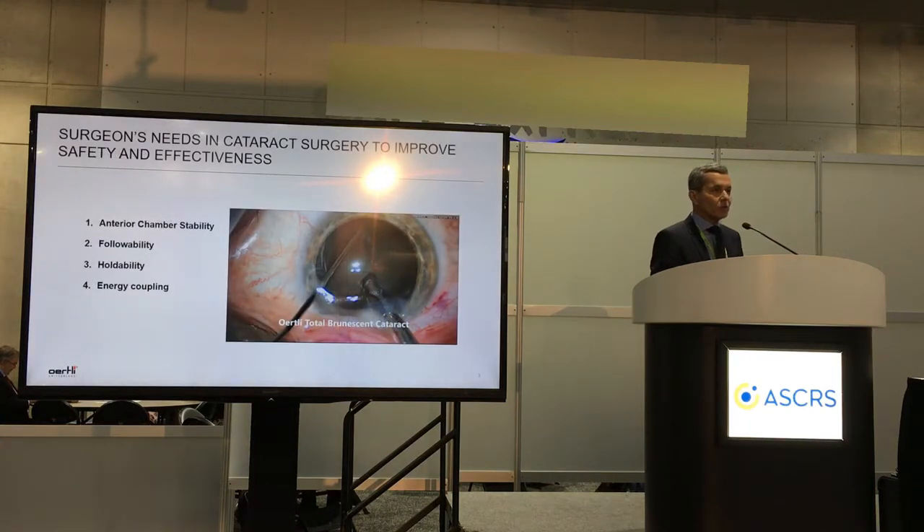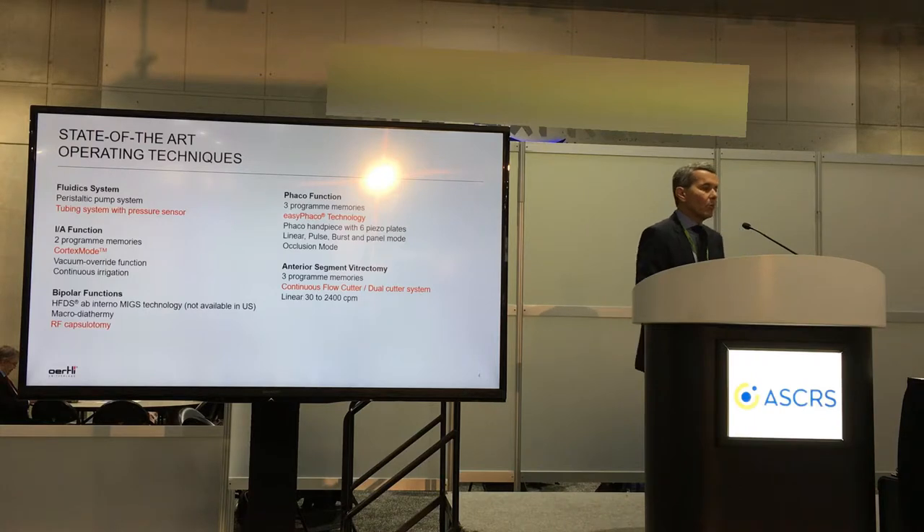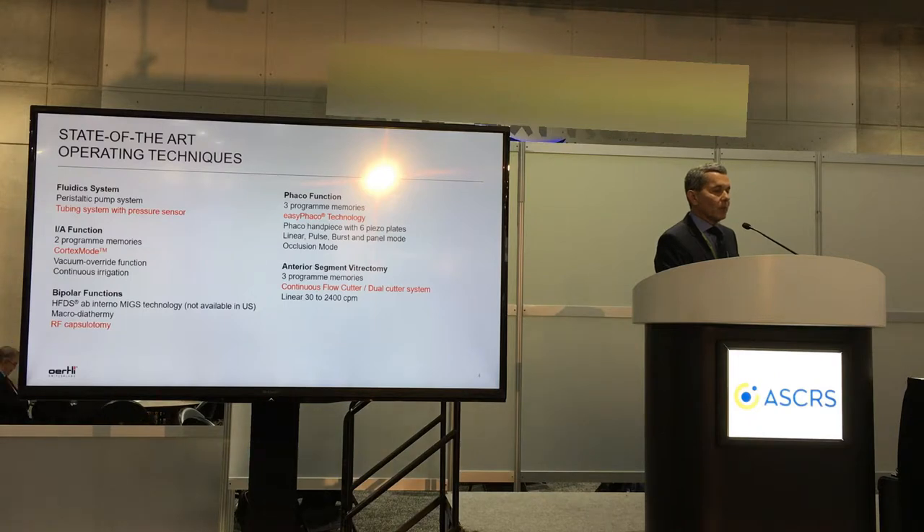As surgeons, we have needs during cataract surgery to improve the safety and effectiveness for our patients. We need anterior chamber stability, good followability, holdability, and exceptional energy coupling. The operating techniques we can do with this machine include a peristaltic system with a pressure sensor, the IA function with cortex mode and bipolar function, especially radiofrequency capsulotomy, anterior segment vitrectomy, and especially the easyPhaco technology.